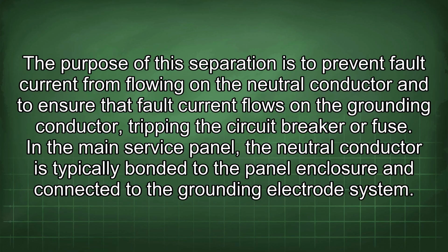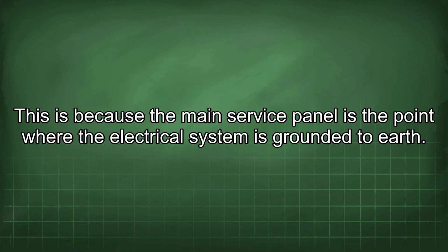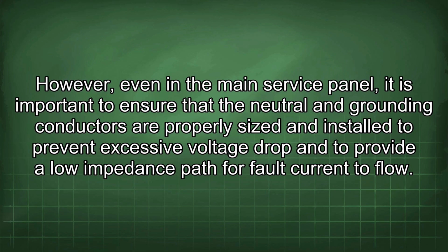In the main service panel, the neutral conductor is typically bonded to the panel enclosure and connected to the grounding electrode system. This is because the main service panel is the point where the electrical system is grounded to earth. However, even in a main service panel, it is important to ensure that the neutral and grounding conductors are properly sized and installed to prevent excessive voltage drop and to provide a low impedance path for fault current to flow.